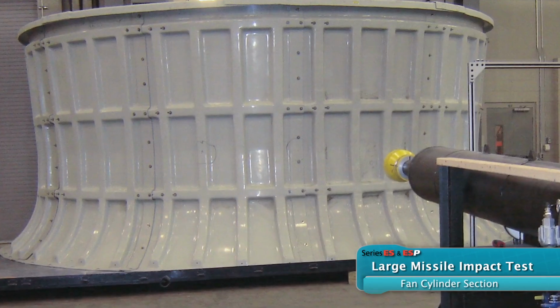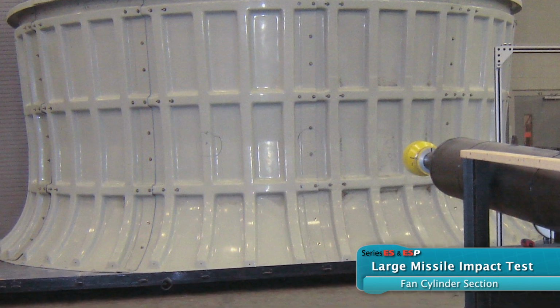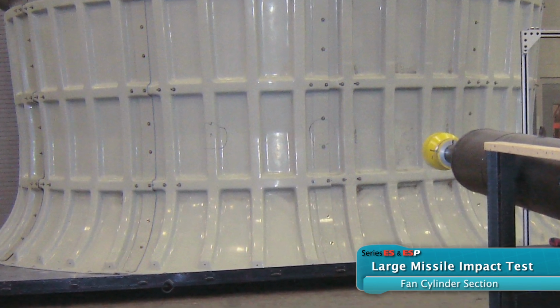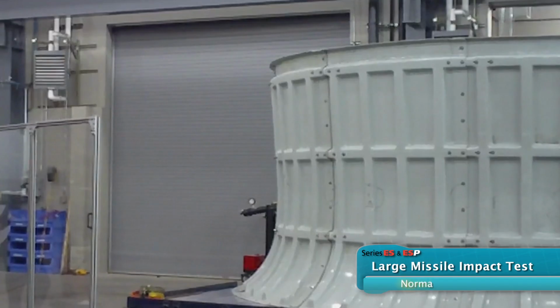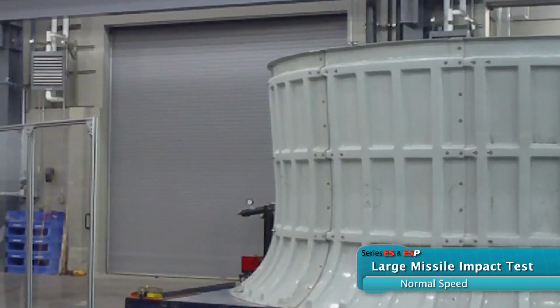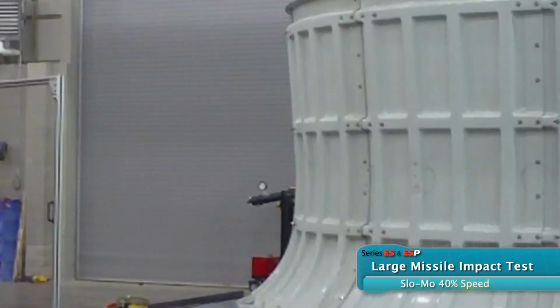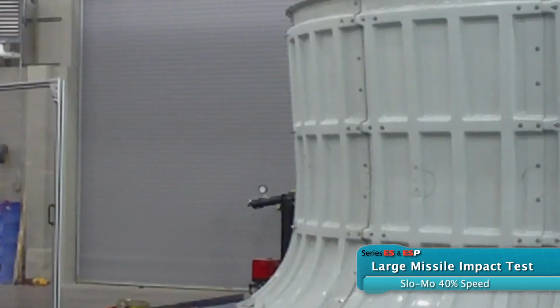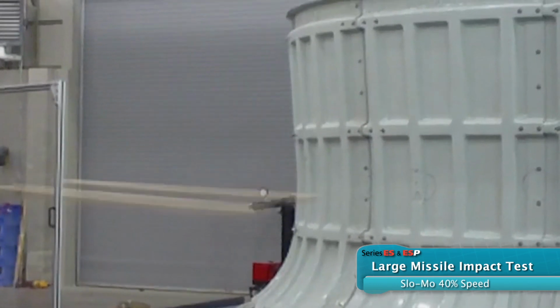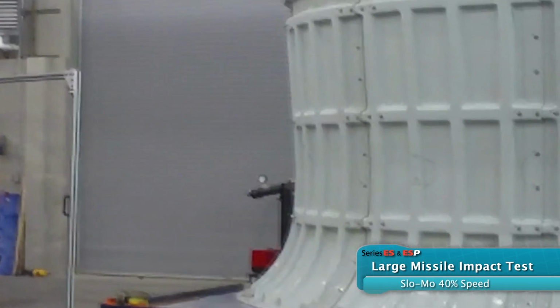In addition to that, the fan cylinder testing required a 2x4 to be shot at the fan cylinder segment, and our fan cylinder showed no detectable deflection in the throat area where the fan blade is, meaning that the fan would still be able to operate even after being hit by the 2x4 missile. The end goal is to make sure the cooling tower operates after the storm.